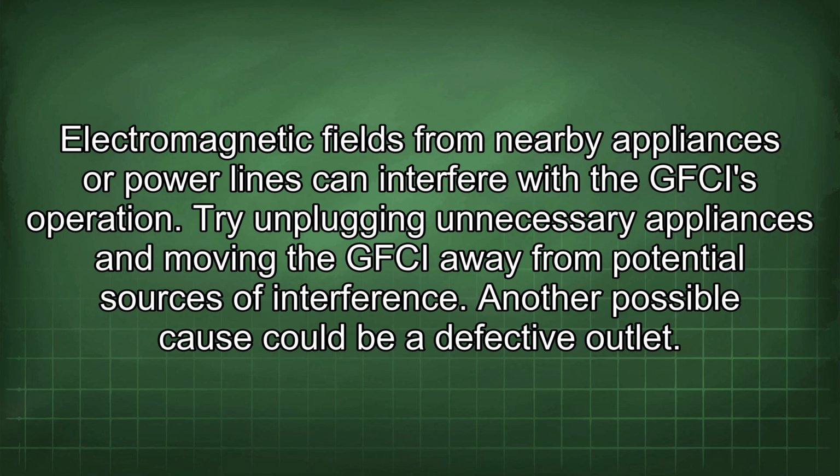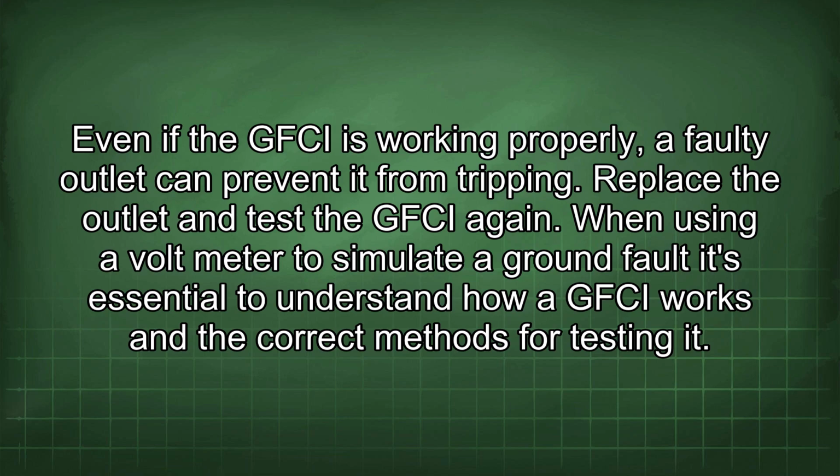Another possible cause could be a defective outlet. Even if the GFCI is working properly, a faulty outlet can prevent it from tripping. Replace the outlet and test the GFCI again.